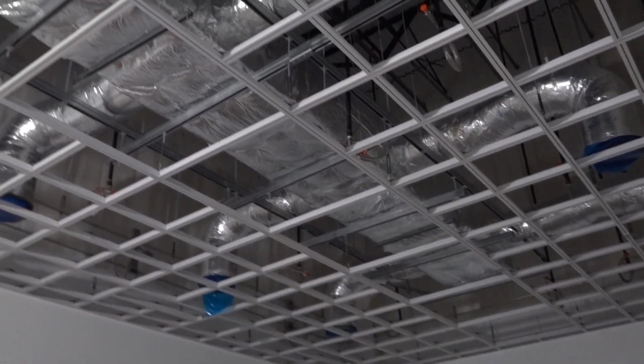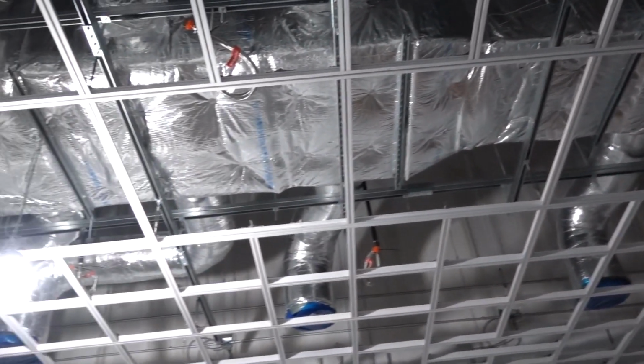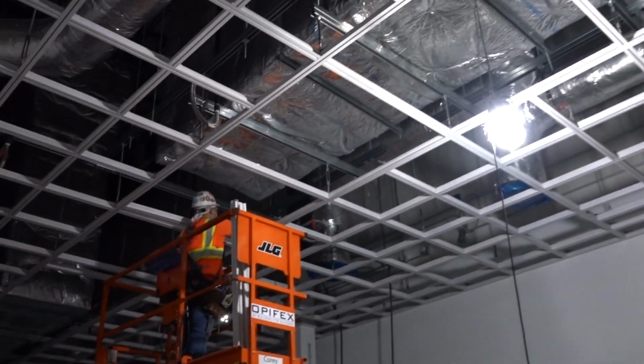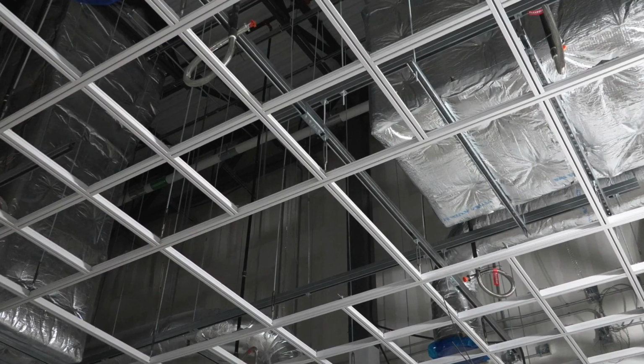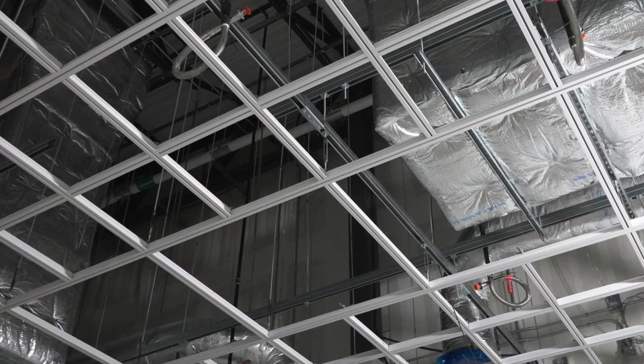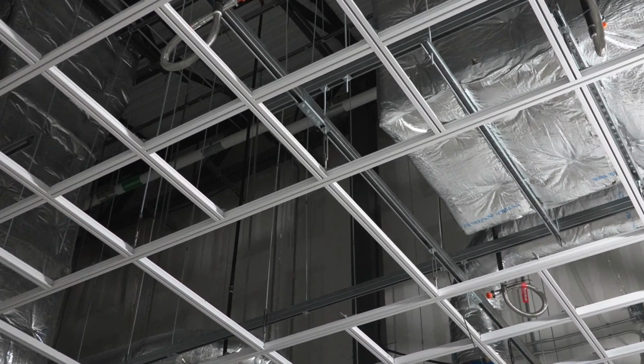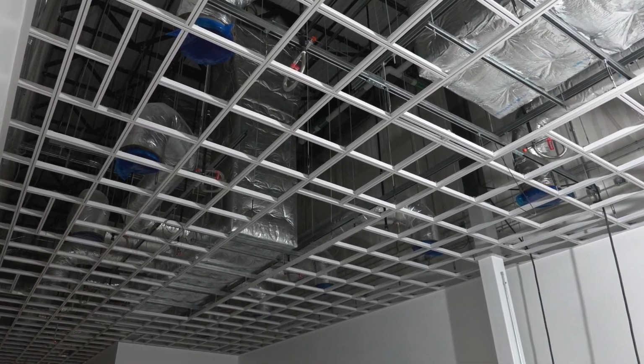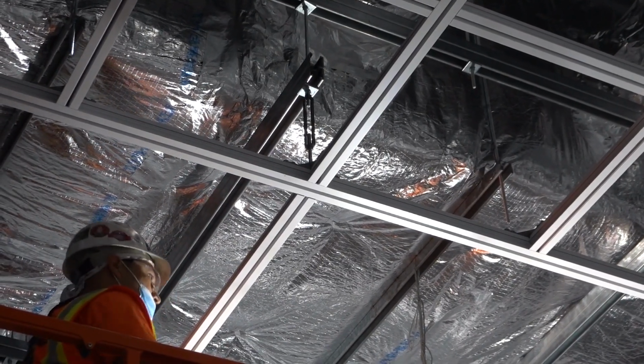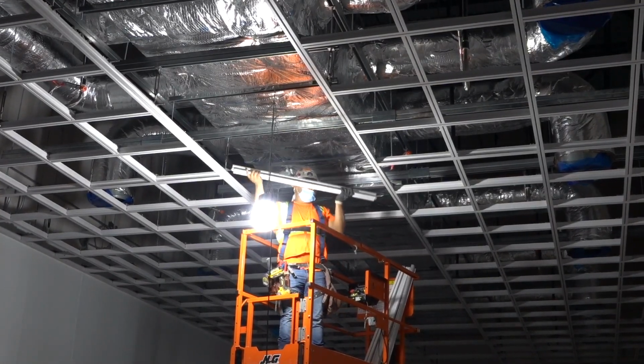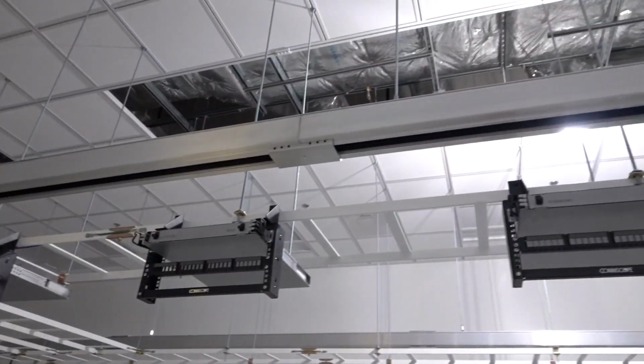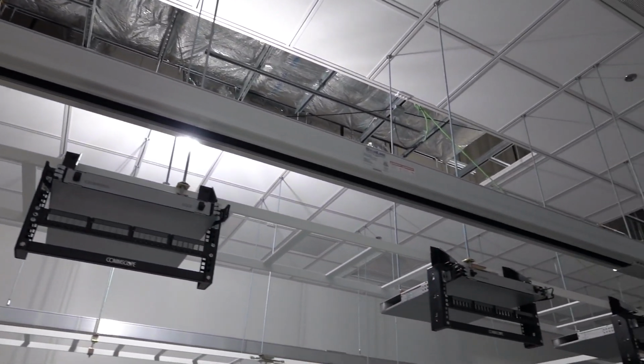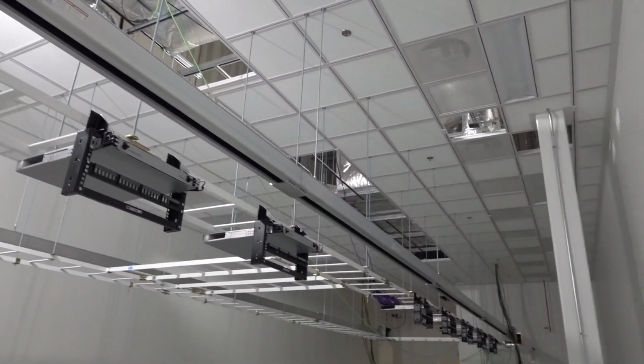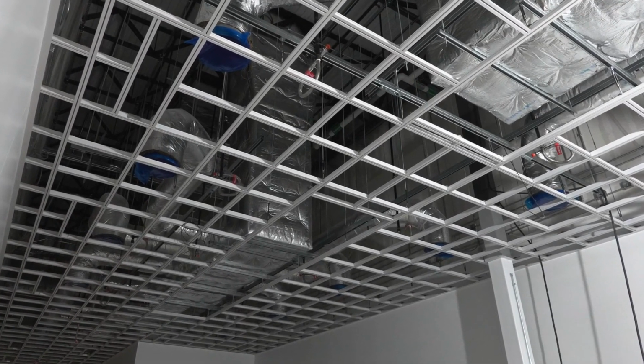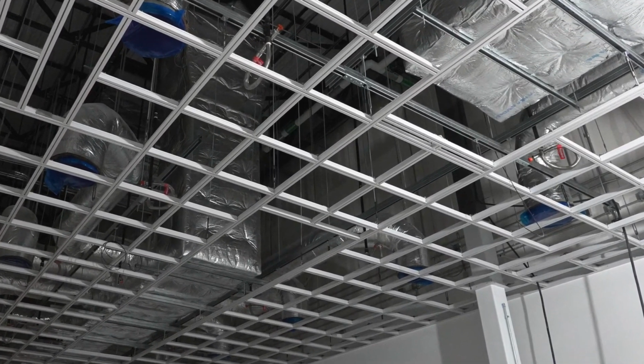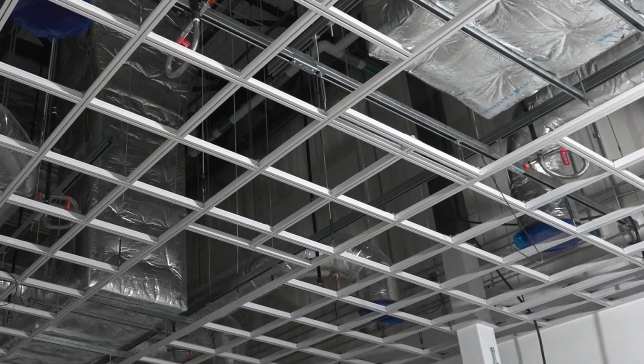When the contractor laid out this 2x2 data hall, they left repeating 4x4 openings down the center of the room. Going wall to wall with the 4x4s in the middle made it easy to alter the middle later for ultimate hot aisle containment areas. Now they're going to go back and take out most of the 4-foot cross tees so they can create 20-foot long by 4-foot wide hot aisle containment zones, then utilize 4-foot and 2-foot cross tees to frame out alternating 5'6" modules that will receive panels between the hot aisle containment runs.